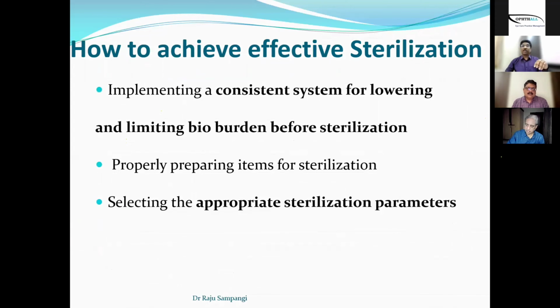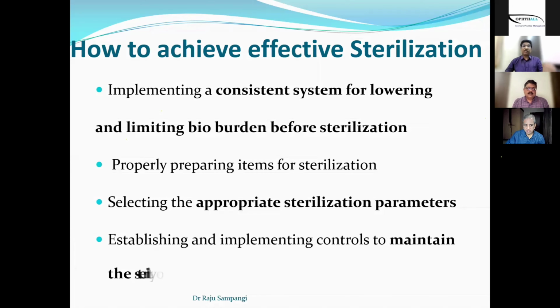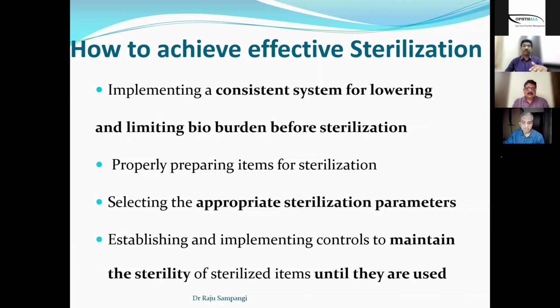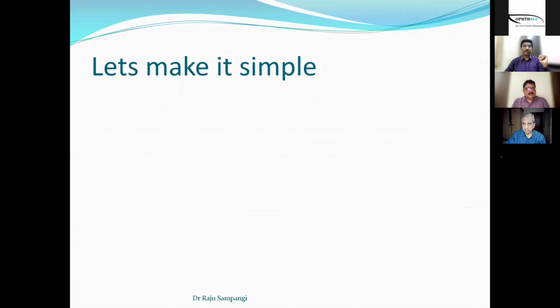How do we achieve effective sterilization? We have to implement a consistent system for lowering the bioburden before starting the sterilization itself. Properly preparing the items for sterilization is as important as the sterilization process itself. Once we are doing a sterilization, we should select appropriate parameters, and establish and implement controls to maintain the sterility of the sterilized instruments till they are used. This is how we can achieve effective sterilization.